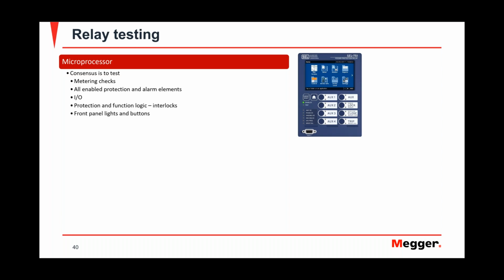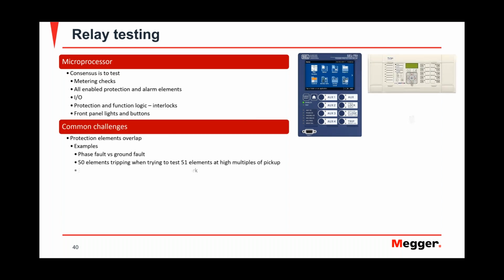Make sure that the front lights and the buttons work. These are all the things that you should do while you test the relays. Some common challenges are when elements overlap. Now that you have multifunctional microprocessor relays looking at 10 different elements virtually at the same time, you could have some phase faults that are going to trip on ground faults if you're doing a single phase test. You may have a 50 element tripping when trying to test a 51 element at high multiples of pickup.